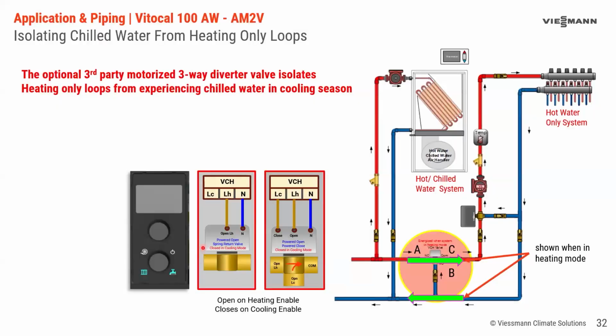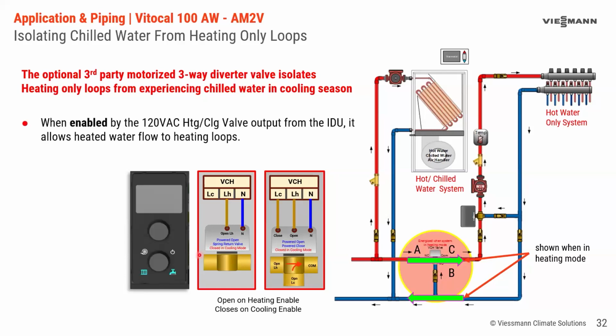So when we look at the control here, we can say that in the heating mode, it will allow water to flow through here. So we're going to power the LH, and that means we're going to have an open circuit here. That's a little different than the other valve we looked at, so make sure we pipe the valve correctly. We're going to want water passing through here in heating mode. So when the unit is in heating mode, the VCH output will power LH.